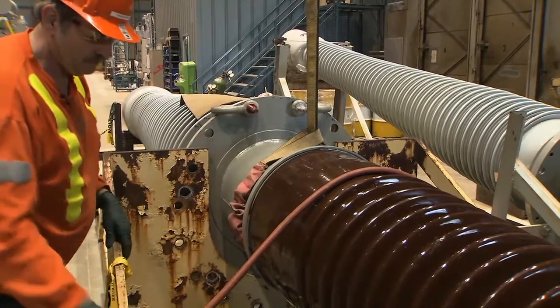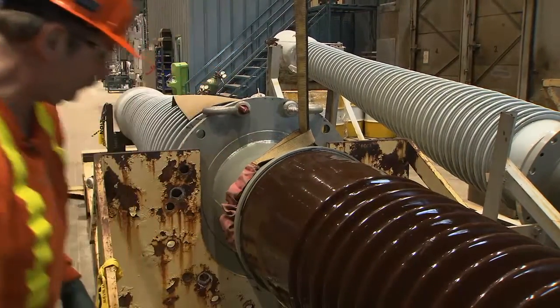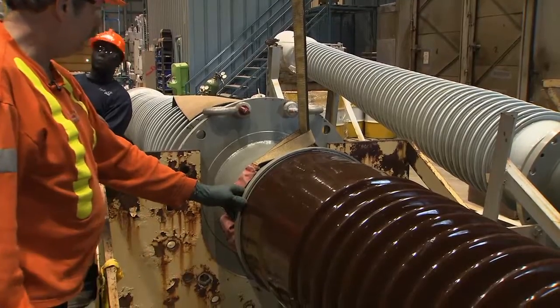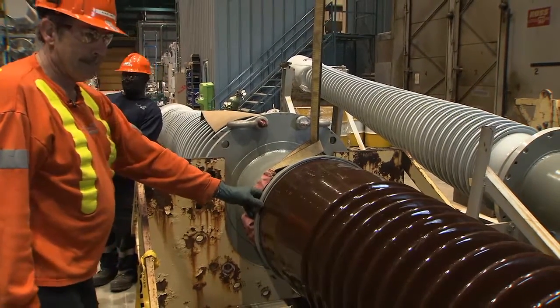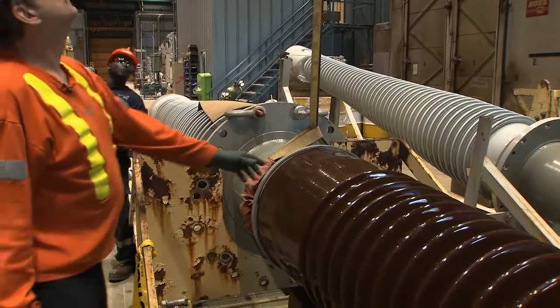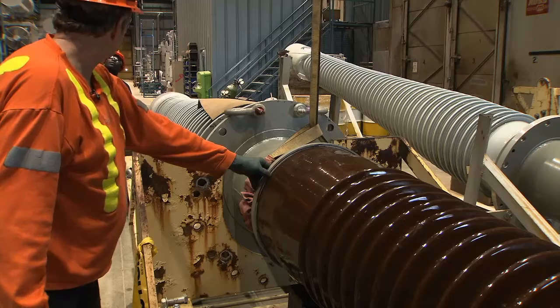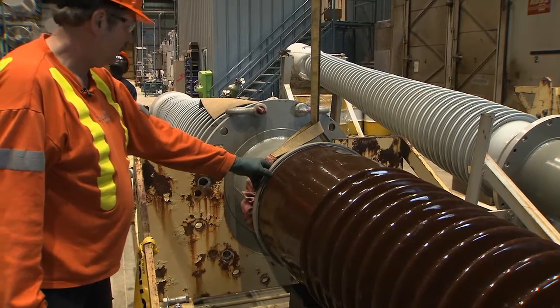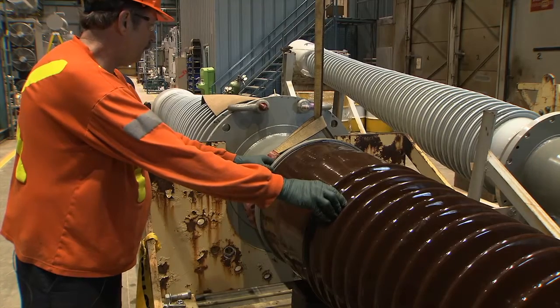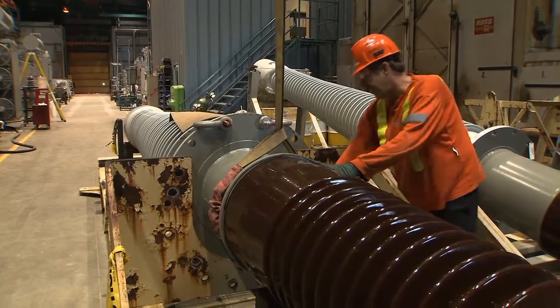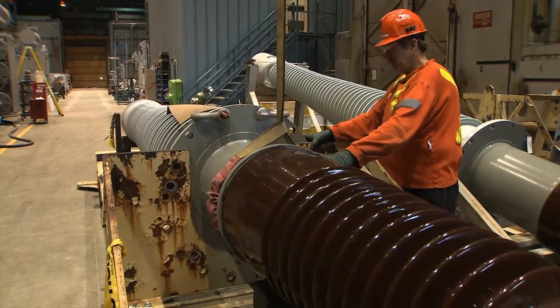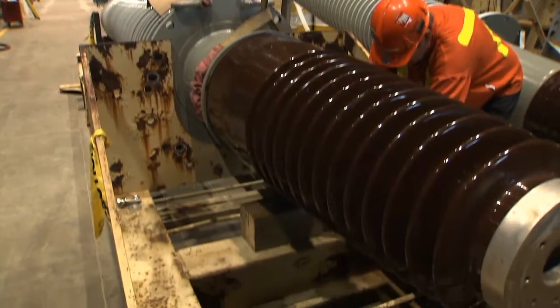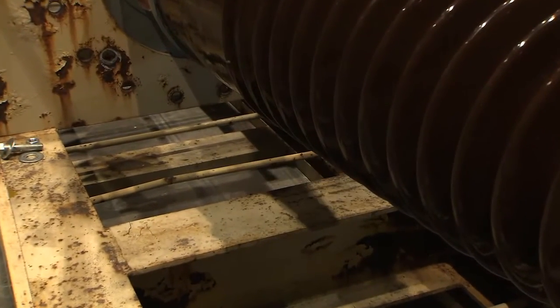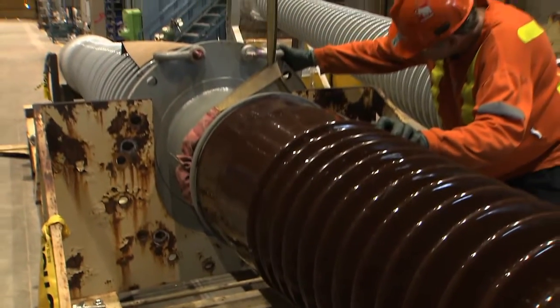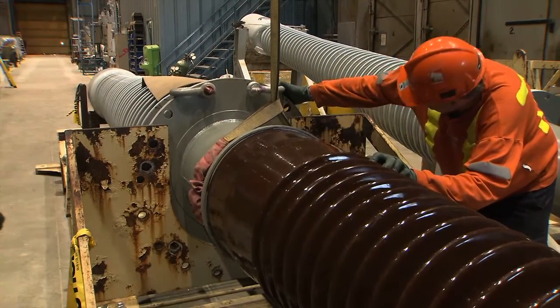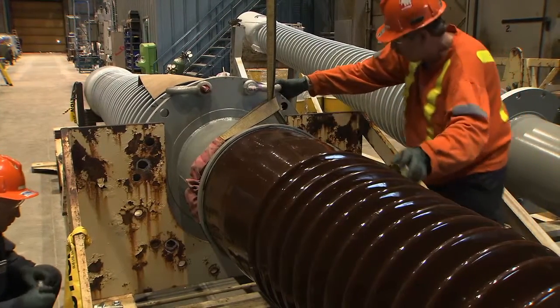Okay. With a sling choked around the ground sleeve, remove the slack by raising the hoist hook. The shackles attached to the flange will not be required in this configuration. Raise the bushing slightly and remove the stack of blocks that the bottom porcelain was resting on. You're already tight against the back here. Okay, I'm going to remove the blocks. Okay, you can start lowering it. Lower the bushing back down in very small increments to line up the holes in the flange with the holes in the transport carrier.